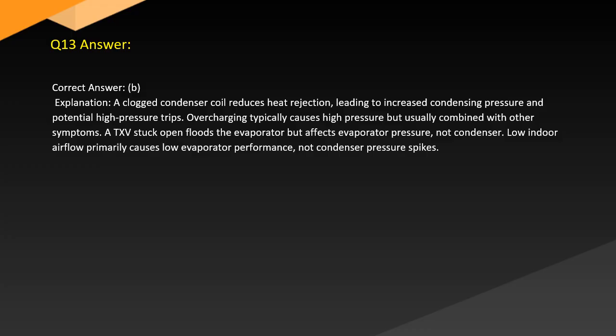Answer. Correct answer: B. Explanation. A clogged condenser coil reduces heat rejection, leading to increased condensing pressure and potential high-pressure trips. Overcharging typically causes high pressure, but usually combined with other symptoms. A TXV stuck open floods the evaporator, but affects evaporator pressure, not condenser. Low indoor airflow primarily causes low evaporator performance, not condenser pressure spikes.